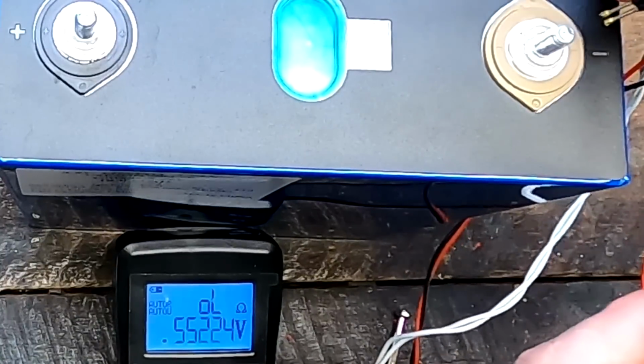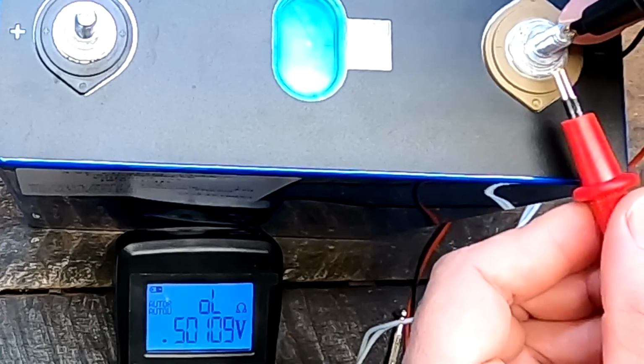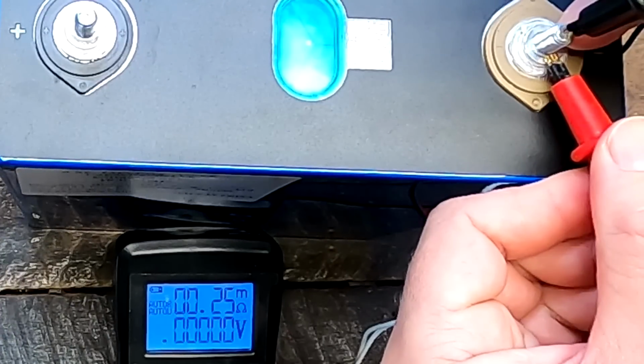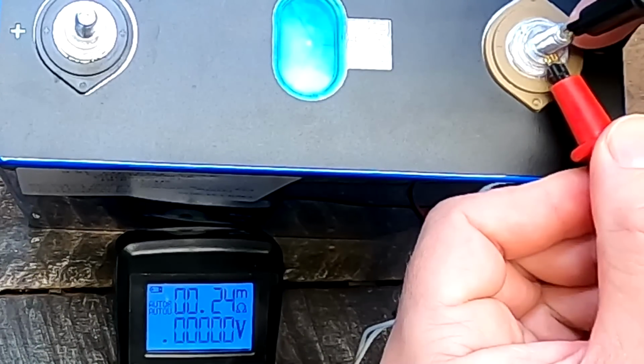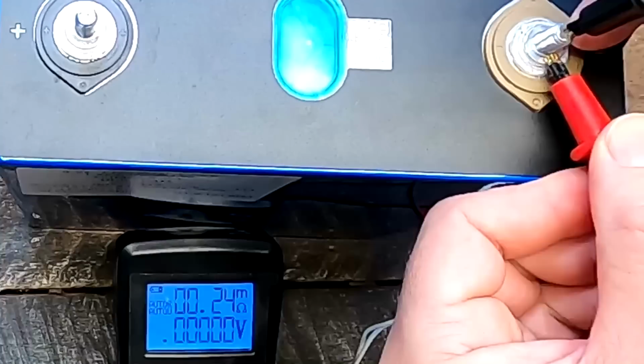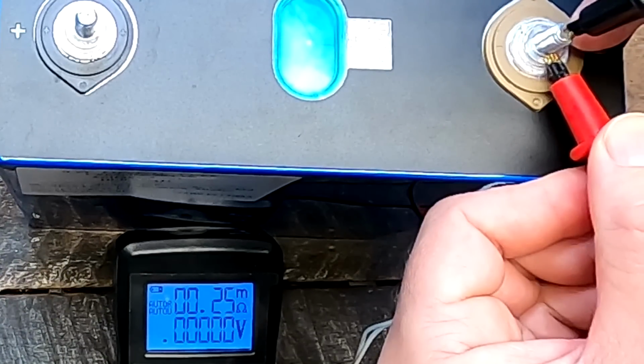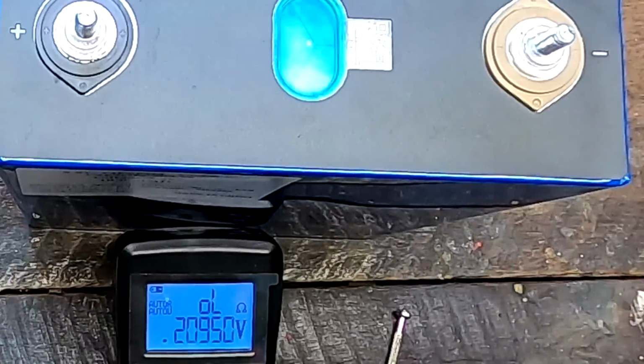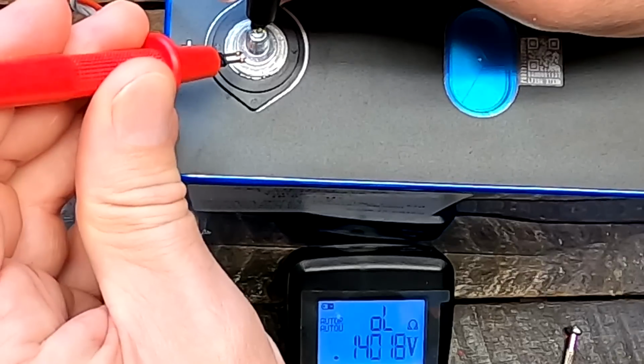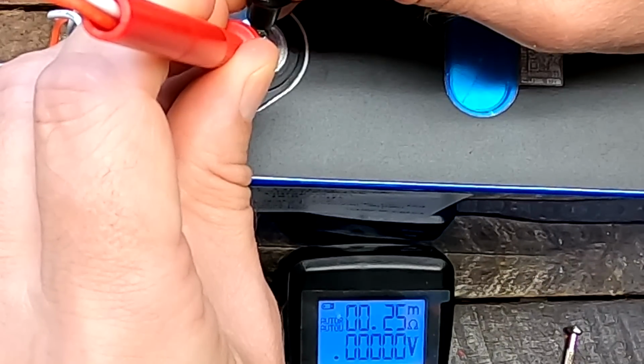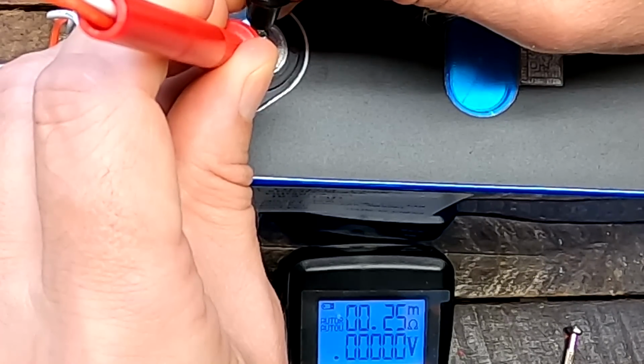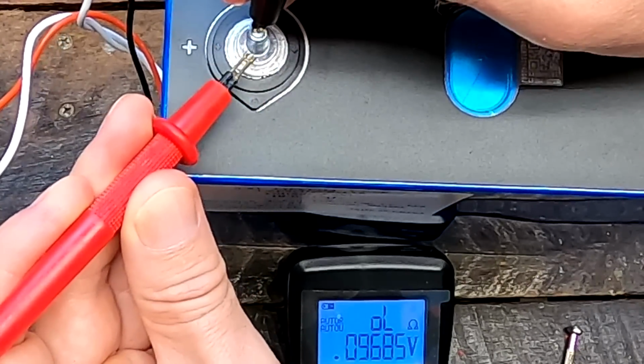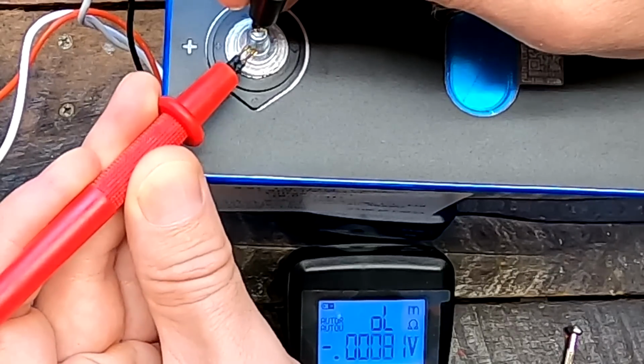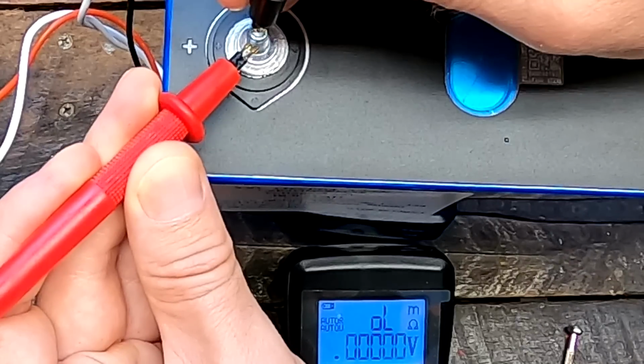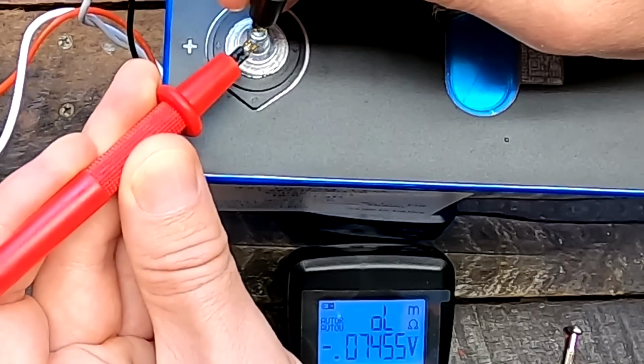So now we can measure one of the studs from the top to the bottom. Here you can see the threaded stud alone has 0.24 milliohms from bottom to top. I'll do the same here — one probe on top of the stud, the other on top of the polished terminal where the bus bar usually sits — 0.25 milliohms. This is just the threaded rod. If we test again, moving the probe up a little, you can see the further up we go, the lower the resistance.